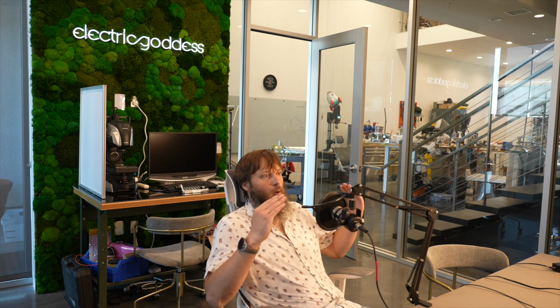It depends on the surface energy and geometry of the point, but a water droplet can bridge a gap of 8 to 10 millimeters and stretch across that surface, maintaining a bridge. If those points are between different voltage potentials, this rapidly consumes one side as an anode by electrolysis, piling up electrolysis products on the cathode side, growing a solid bridge from what was once just a drop of water.